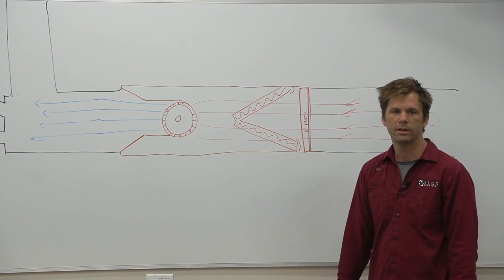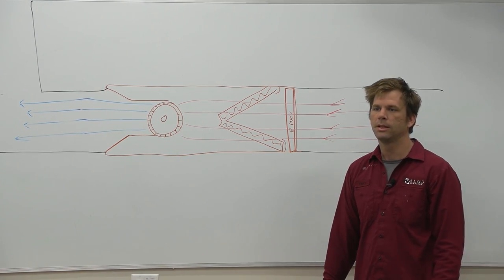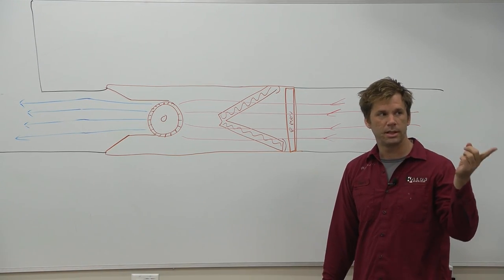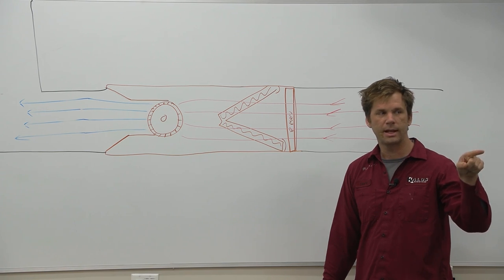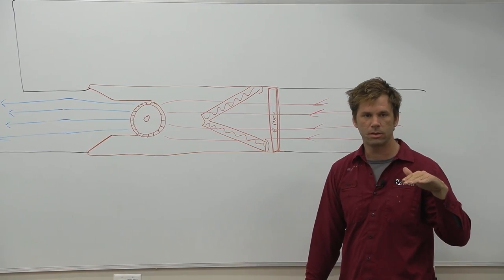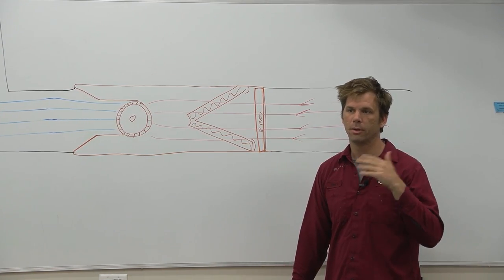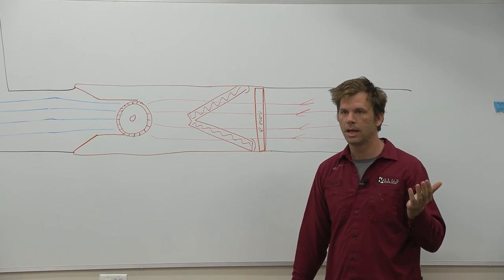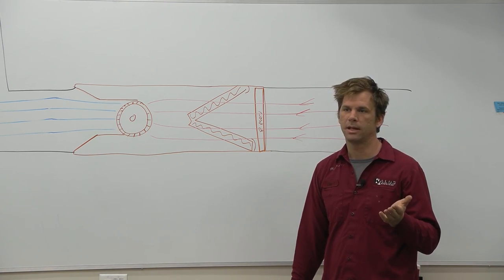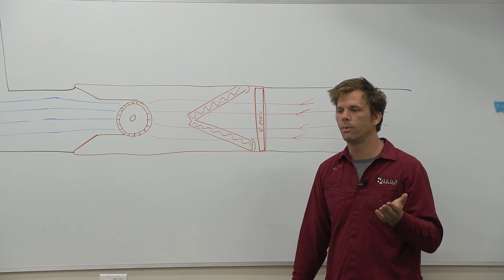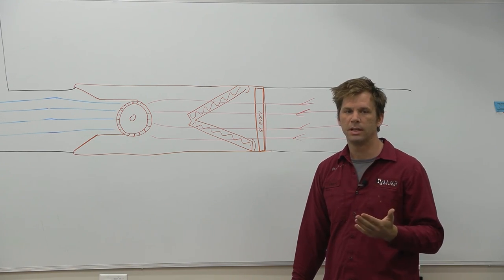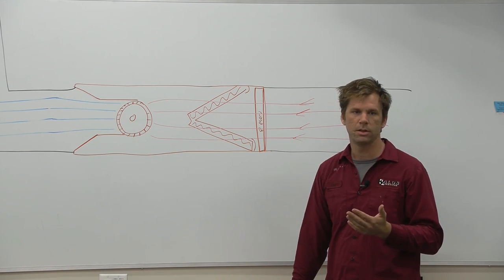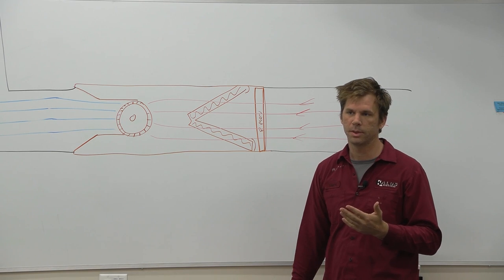Our external static pressure is taken above the filter and then on the outlet before the rest of the ductwork. This is measuring just our system as it would come from the manufacturer. You'll see external static pressure listed on your data tag. It'll tell you what the manufacturer used to test and get all of their performance data. You'll see external static pressure used when you're looking for setting blower speeds.